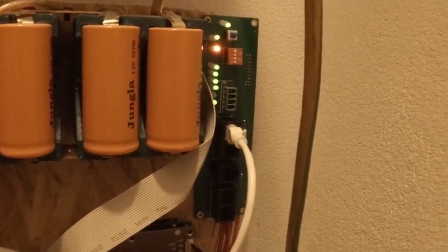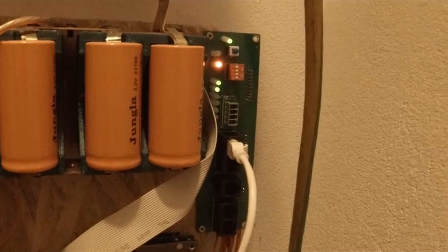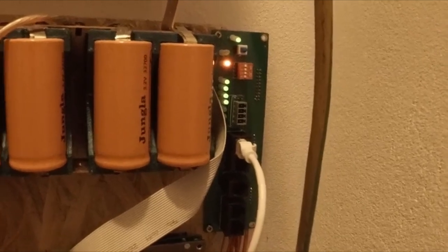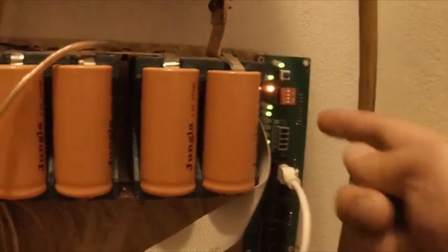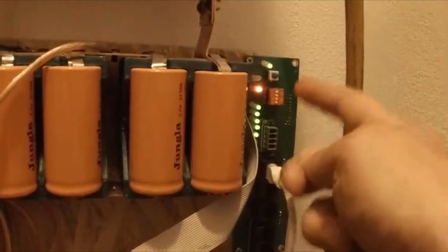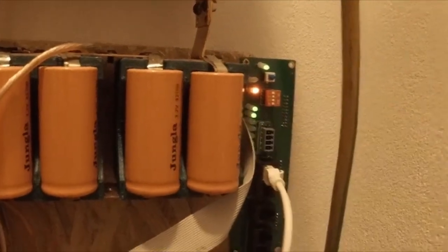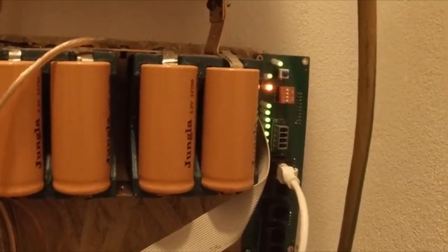A very important thing: this device connects via RS485, and as you know, RS485 requires an address. The address of this device must be address 0. We set the address here with these switches—all 4 must be off, meaning everything is set to 0, meaning address 0. This is very important.